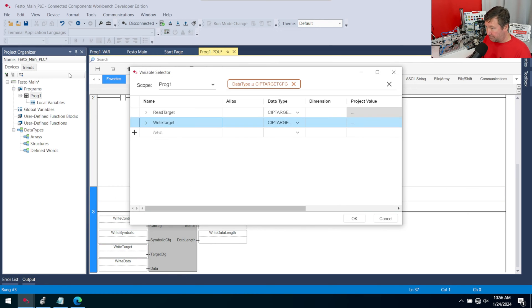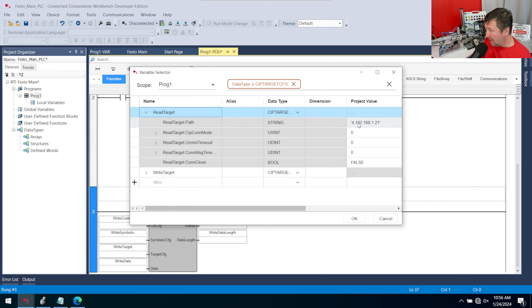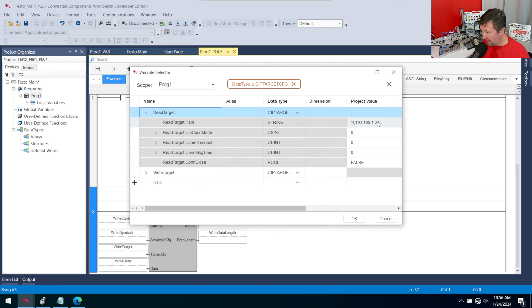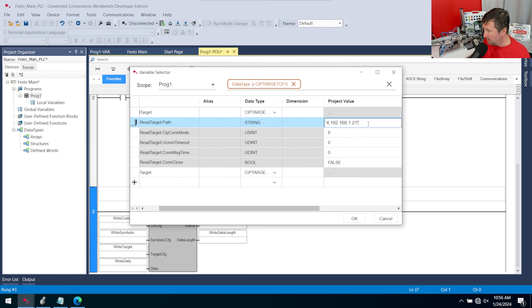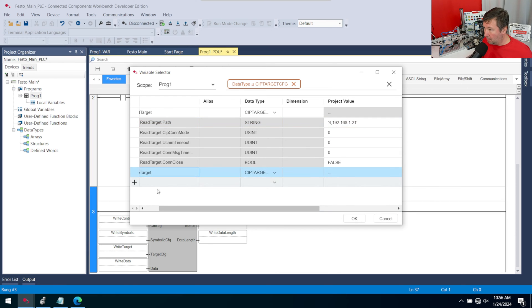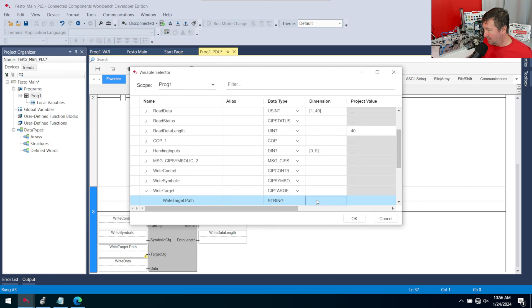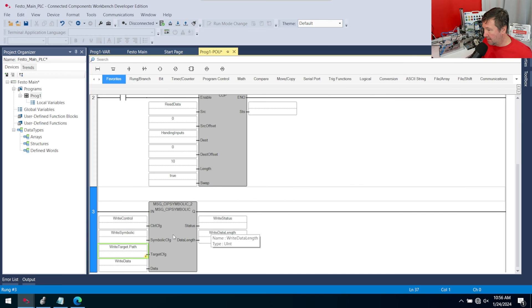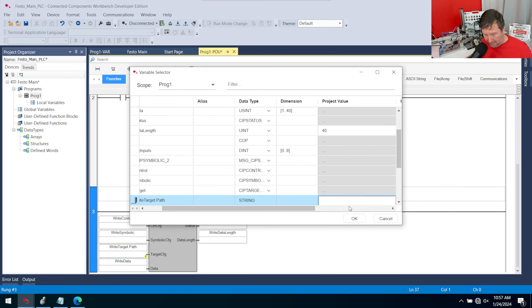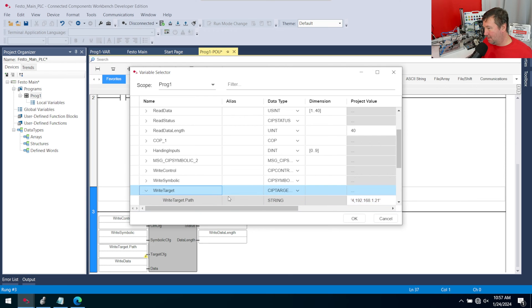Now we have our write target. Let's open our read target for a quick recap. We have port 4, which is the Ethernet port on the Micro 800 that you want to send this message out of. Then we have the IP address of our target PLC — in this case 192.168.1.21. We can leave the rest at their default values. I'm going to copy this and paste it into our write target.